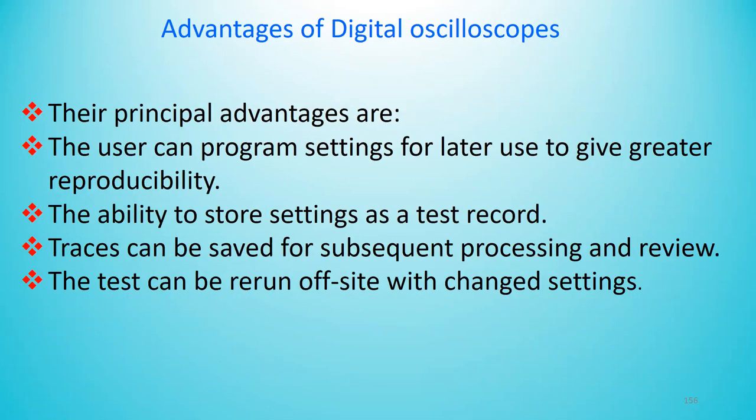The principal advantages are that the user can program settings to be used later, giving greater reproducibility. There is the ability to store settings as a test record in digital oscilloscopes. The traces can be saved for subsequent processing and review. The test can be rerun offsite with changed settings.